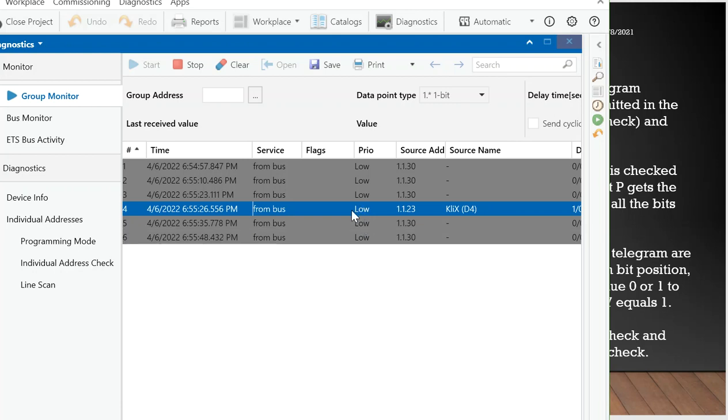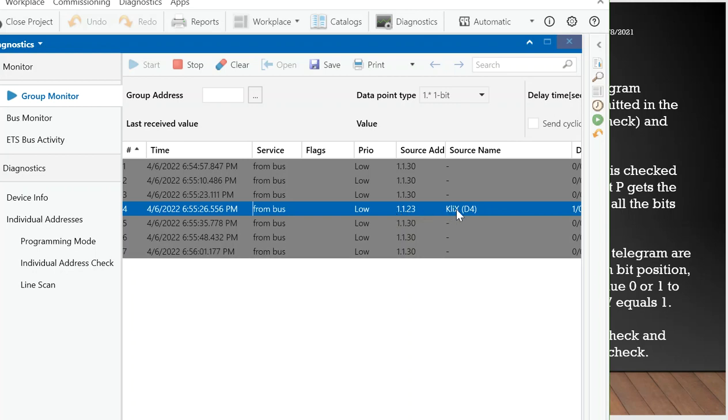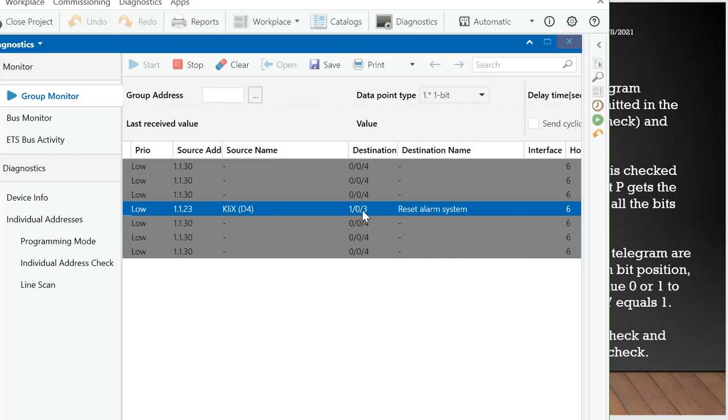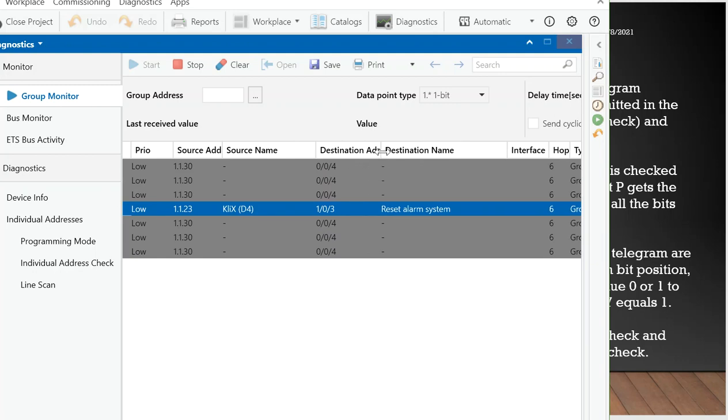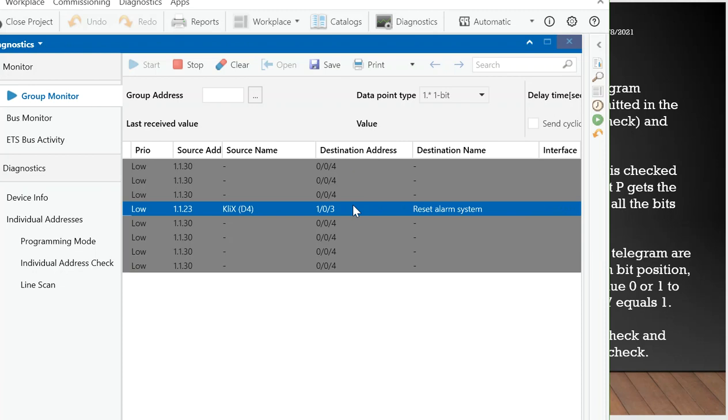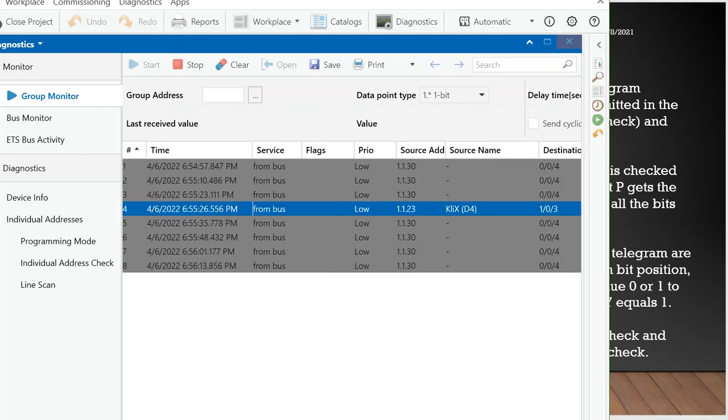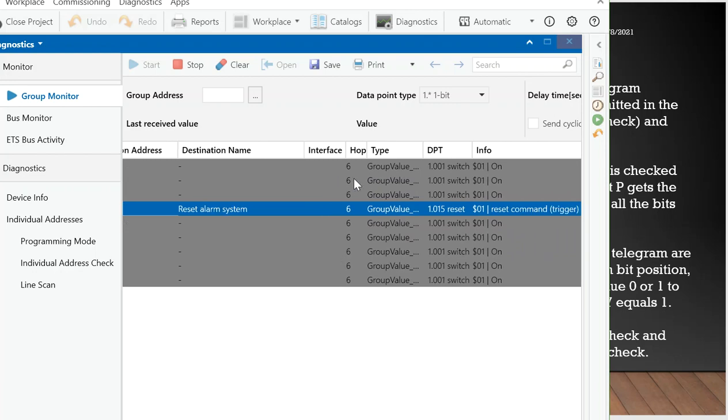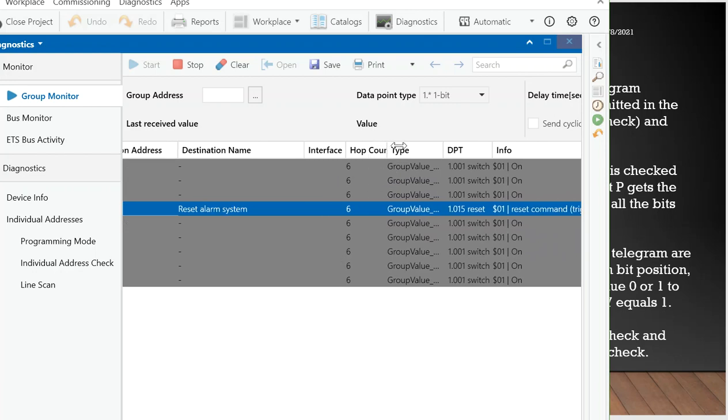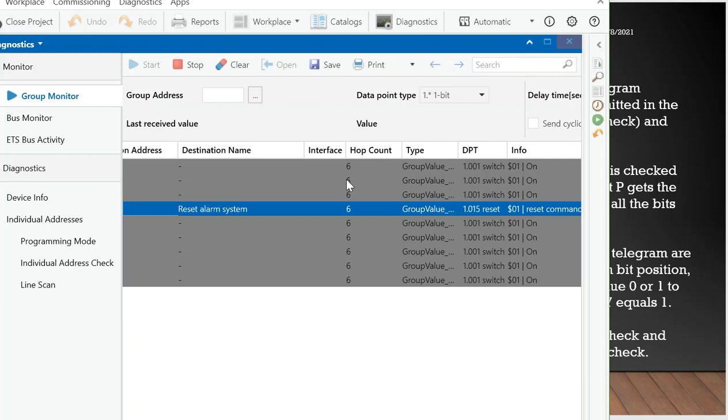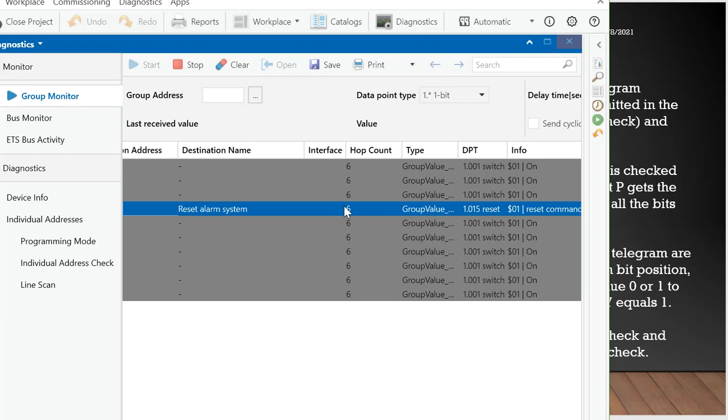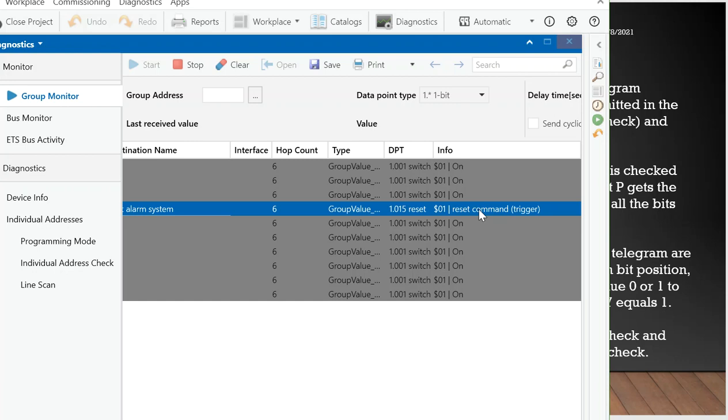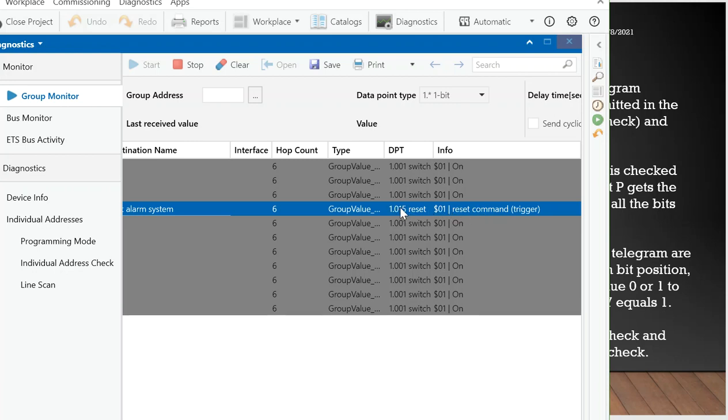You can see this telegram. What sent this telegram? This telegram is sent from some specific time. The priority is low. You remember that we talked about the priority, it is mentioned in control field. Then the source address, what is the source address? This is in our example 1.1.23 from the sender, the source name is assigned. Great. The destination address also is mentioned in the telegram. And the destination name, so the destination is a group address, the source address is a physical address because you remember we clicked. The destination name, the route counter, so here in ETS6 it's named hop count. This is six because it does not go through any router or coupler. And then the important is useful data and this is useful data. This is a reset command. This is one bit reset command. And this is a data point type 1.015 in our example.